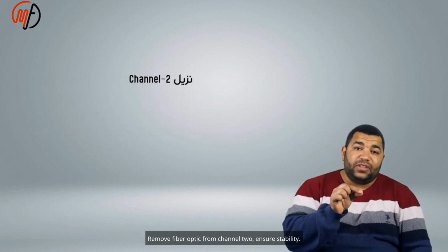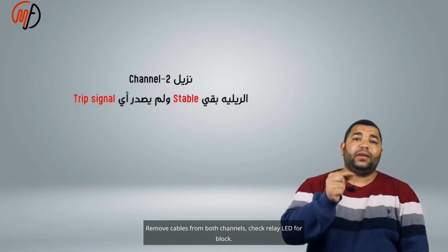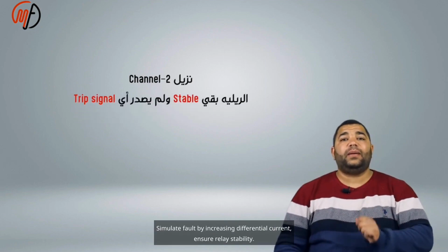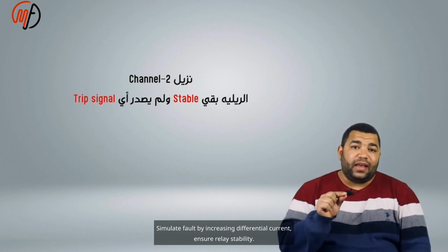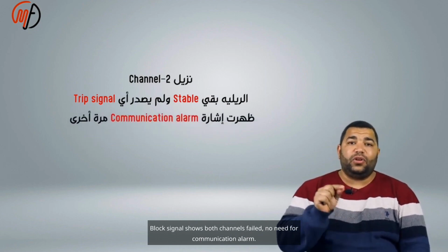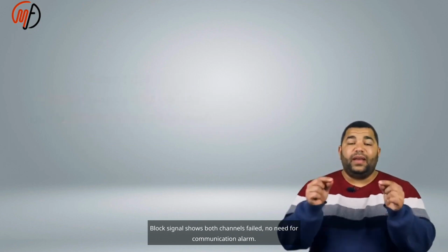Remove the fiber optic from channel 2, ensure stability, and the alarm reappears. Remove the cables from both channels, check the relay LED for the block, simulate a fault by increasing the differential current, and ensure relay stability. The block signal shows both channels failed, so there is no need for the communication alarm.